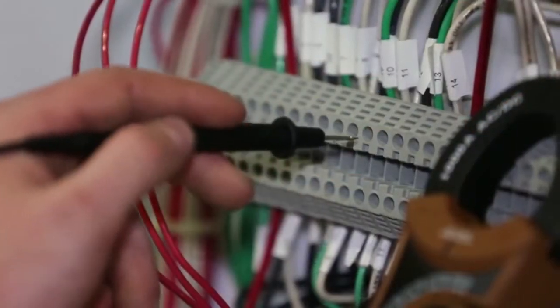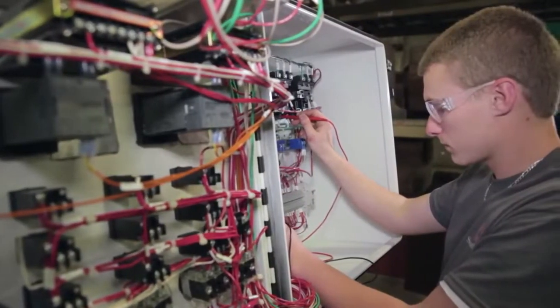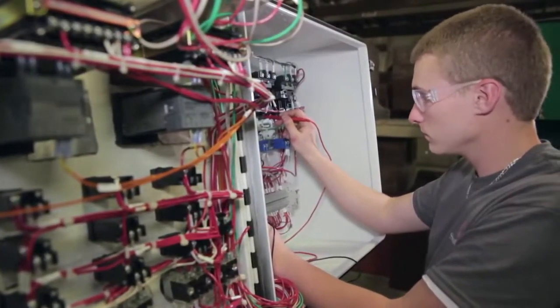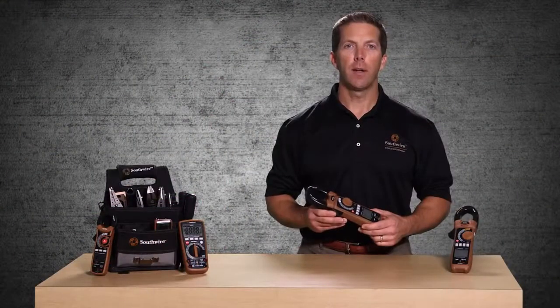True RMS readings provide more accurate AC voltage and current readings in the presence of harmonic distortion. This distortion is common on electrical loads such as fluorescent lighting, computers, and other electronic devices.